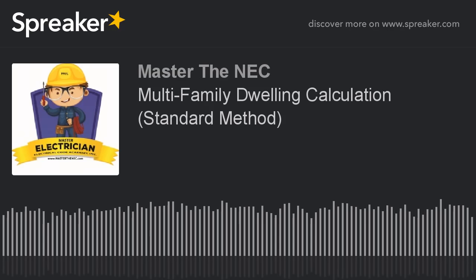And I'm going to do this with you, if you're following along. It is 9.8, and we're going to do that times 120, because that's what the voltage is, times 18 units, and that is 21,168. So that is our air handler load that's in every unit, okay, and there's 18 of them, so that's the total.